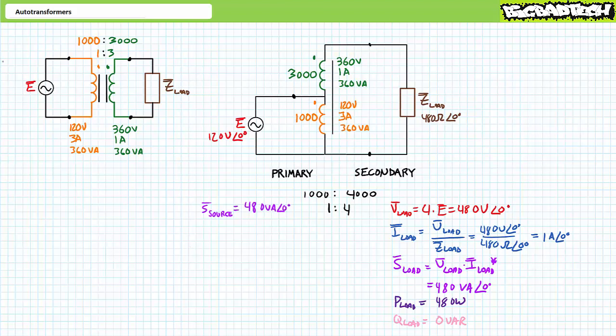Assuming the autotransformer is 100% efficient, power in equals power out, so the primary input side must also supply 480 volt amperes of apparent power. An algebraic manipulation of the power equation solving for current demonstrates the primary input side of the autotransformer must draw 4 amps of current from the 120 volt source.